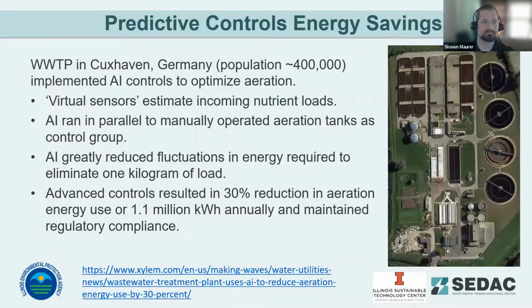Here are some examples of what we've seen with AI automation and predictive controls. There was a wastewater treatment plant that implemented AI controls with virtual sensors ahead of the plant at the influent level, feeding data into the AI system. As a test, they ran this in parallel with their treatment basins, some running on the AI program and some on their traditional process, and found that with the AI system implemented, they had about a 30% reduction in energy use. Once implemented throughout the whole plant, it was about a 1.1 million kilowatt-hour annual reduction in energy consumption. It also greatly reduced fluctuations in the energy required to treat the process, giving more stable operation and optimizing the metric of energy per kilogram of loading coming into the plant.